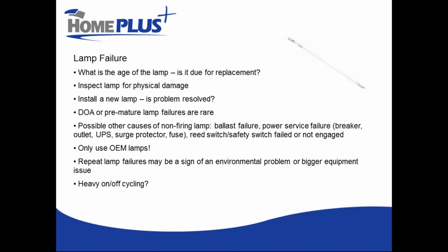So we do find that people replace these probably more than they should or need to, chasing problems that are really something else. But it is important to consider the age of the lamp. Most UV lamps have a 9,000 hour or roughly 1 year life. There are some on the market that are 2 years, but if it has a 12-month life and you're at 11 and a half months, and you're starting to get an intensity or a UV alarm issue, you have to give some consideration to it being a lamp. If the lamp's 2 months old, it's probably much less likely to be the lamp, but it could be.